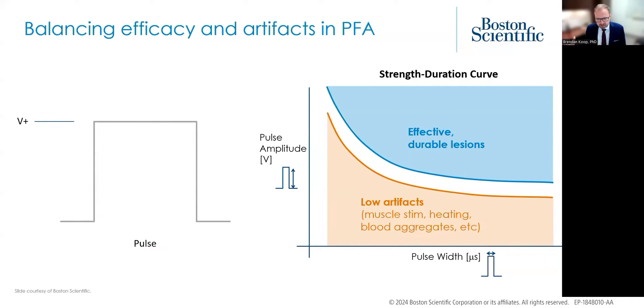One way to boil down a lot of this complexity is to describe pulse field ablation with a classic strength-duration curve, where the y-axis is the amplitude of the pulses and the x-axis is the duration of the energy we're applying. We want to be in the upper right — effective, durable lesions. But we also want low artifacts: low muscle stimulation, low heating, low blood cell aggregation, and prevention of arcing. In practice, it's very difficult to make these two areas intersect. When we start researching pulse field ablation using off-the-shelf catheters, you quickly discover you're either getting a good lesion or you're getting low artifacts, but not both.